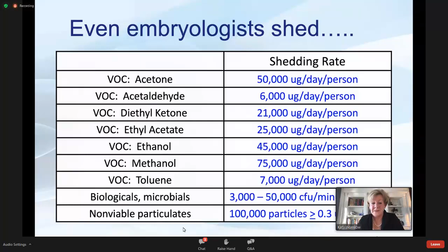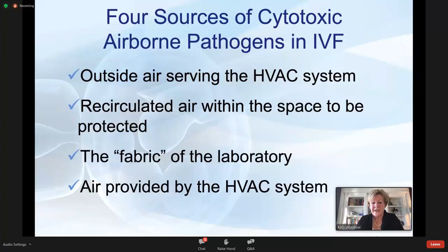Third, the materials that you use in your laboratory. If you're thinking about expanding or building new, be very, very cognizant of the type of materials you're using: your ceilings, your walls, your flooring, adhesives, avoid at all costs. Paint, white. The greater the tint of the paint, the greater the off-gassing of VOCs. Caulking, sealants. And then finally, the air provided by the HVAC system itself. Again, we create the perfect environment for growth. Perfect temperature, perfect humidity. So therefore, the pathogens, the allergens, and the toxins that are in the air going through the ductwork serving your laboratory can continue to grow.